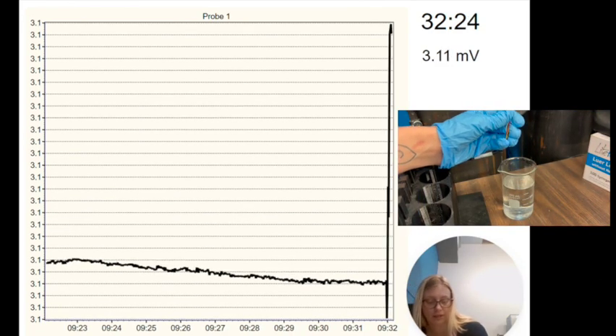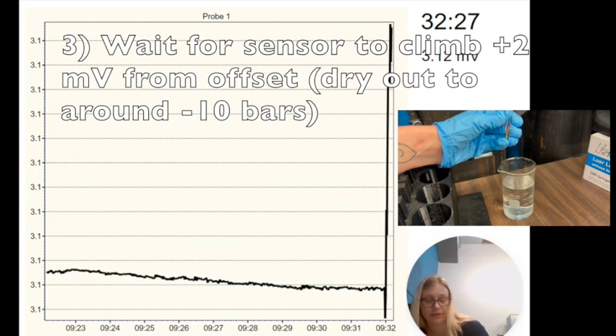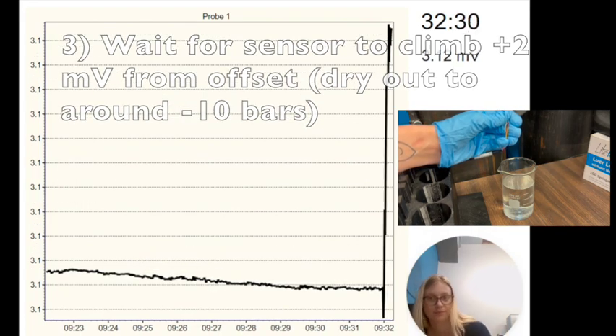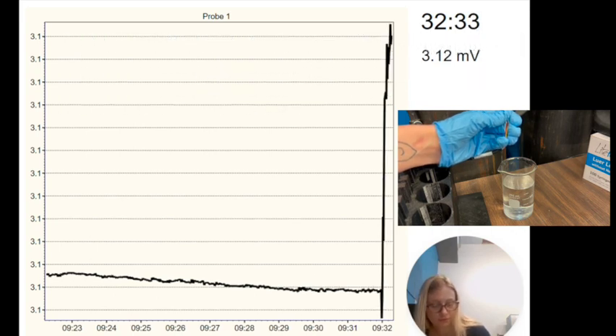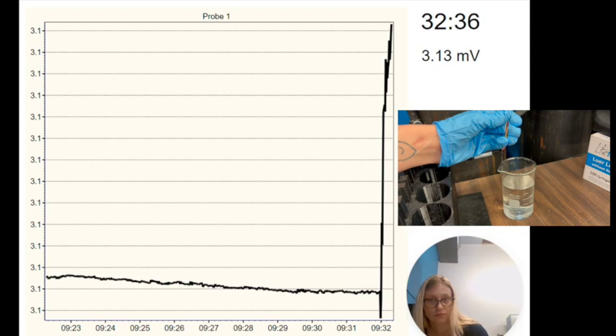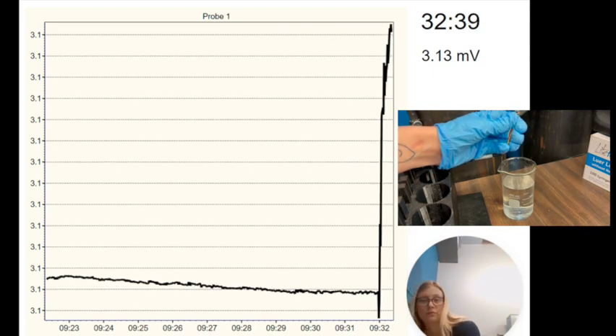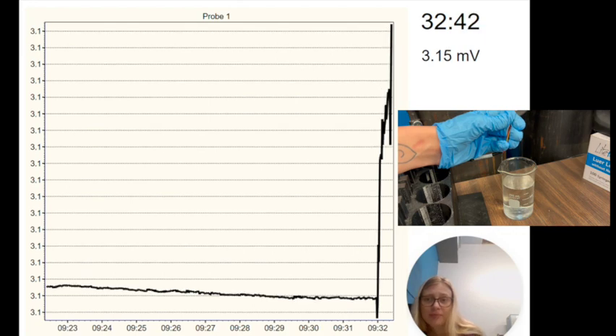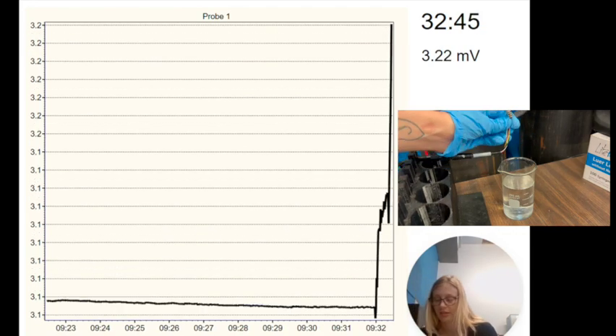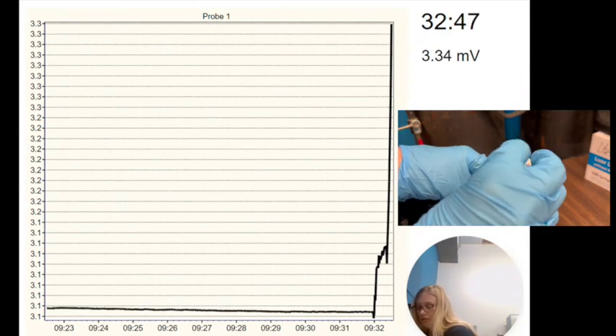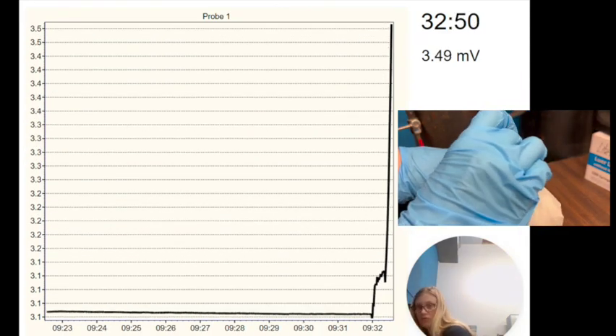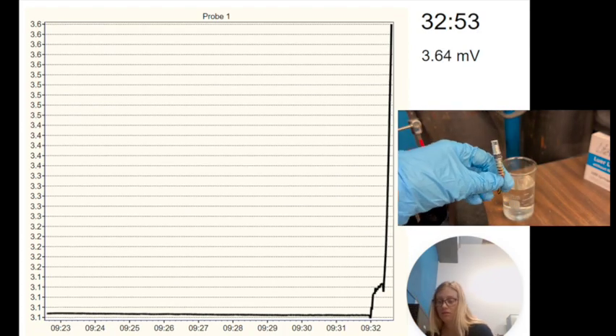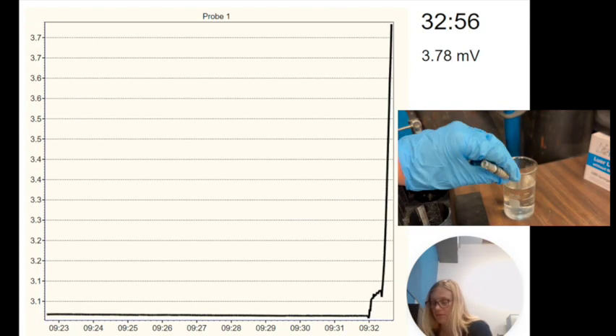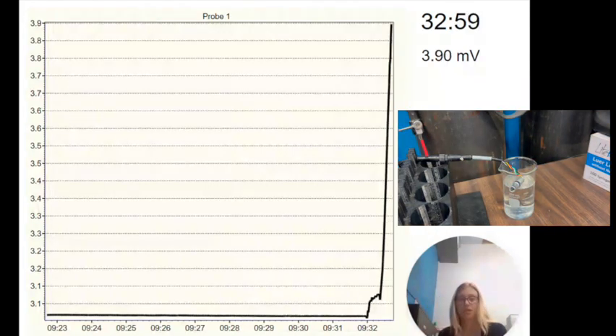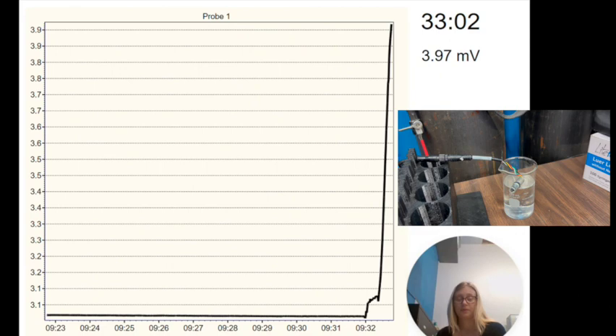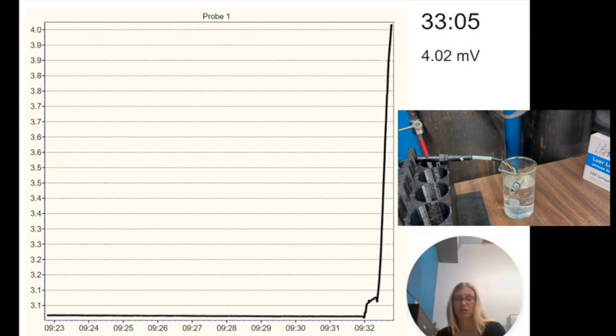And we're going to wait for it to climb to around 5 millivolts. So that's a 2 millivolt difference. And this sensor is responding pretty quickly, so we know that it's drying out okay. I'm going to dab it dry just to make sure. But as we can see in the readout, it's shooting up, so it should be drying out properly. And we'll wait for it to reach a little over 5 millivolts.